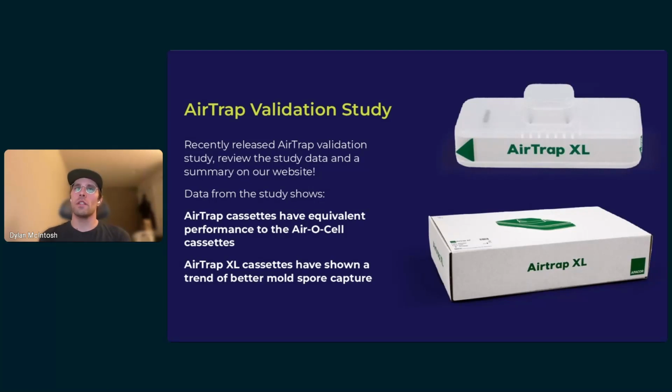But generally speaking, the study showed that AirTrap cassettes are equivalent to the industry standard Air-O-Cell cassette in sampling efficiency, as well as the particulate trace distribution, etc. We have shown to be as good or better than the Air-O-Cell. And then there's also a data trend indicating that the AirTrap XL might actually have better spore capture, meaning it captures more mold spores than the other cassettes out there.